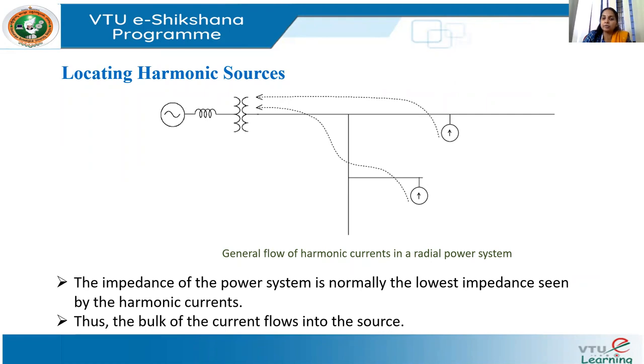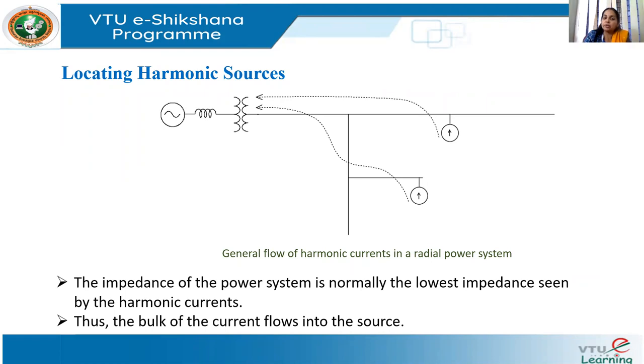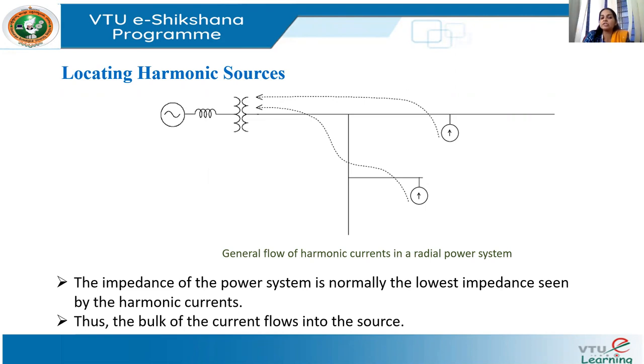If we have a power quality monitor capable of reporting the harmonic content of the current, we can measure the current at each branch of the power system and see exactly from where it is coming. The branch after a particular harmonic-producing load may not carry the harmonic current, but the branch before it will. By checking the harmonic component of the current using a power quality monitoring device, it is possible to locate the sources of harmonic currents.